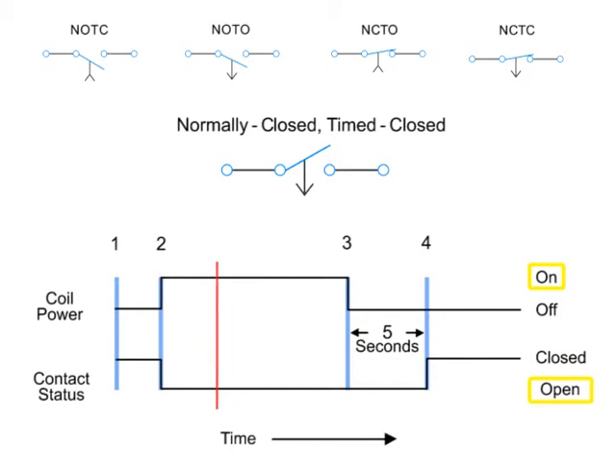However, unlike the NCTO contact, the timing action occurs when the coil is de-energized instead of when it is energized. Thus, the contacts open immediately when the coil is energized and close five seconds after the coil is de-energized.